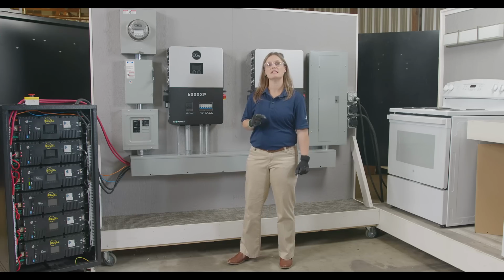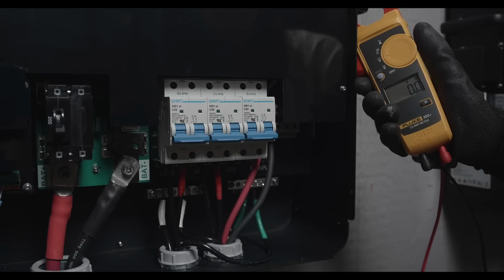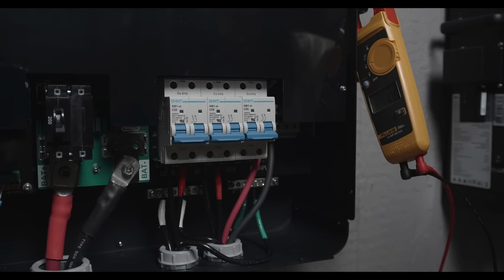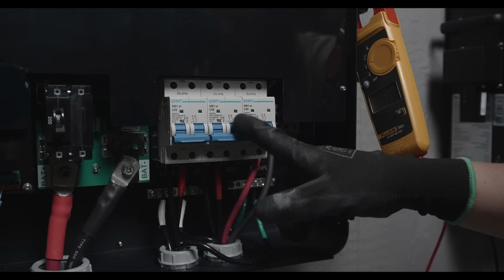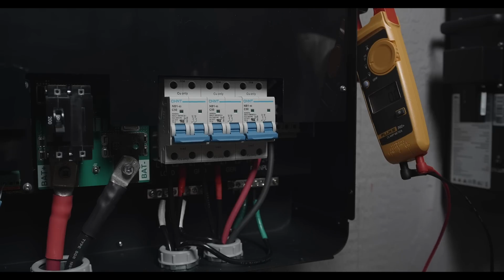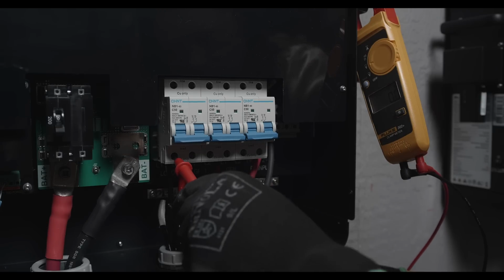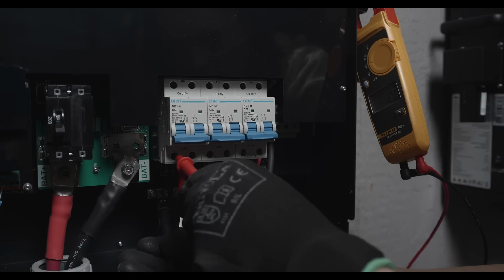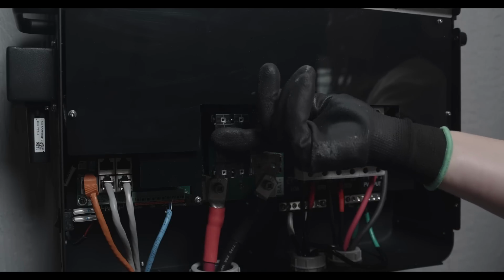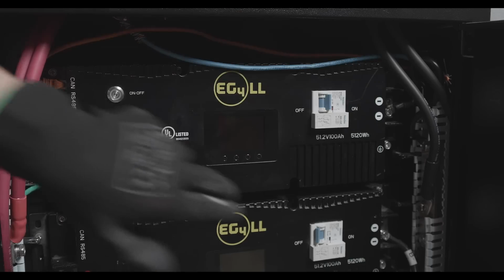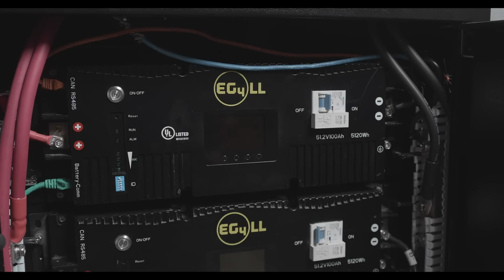If utilizing AC output, double check each hotline to neutral coming into the inverter to ensure voltage is within the operating range of the unit, between 120 and 240 volt AC and less than 9,000 watts. Turn off all your load breakers and confirm no AC voltage with a multimeter. Once confirming that all voltages are within the inverter's operating range, turn on the battery breaker on the front of the unit. And if equipped, turn on the external battery breaker between the battery bank and the inverter.